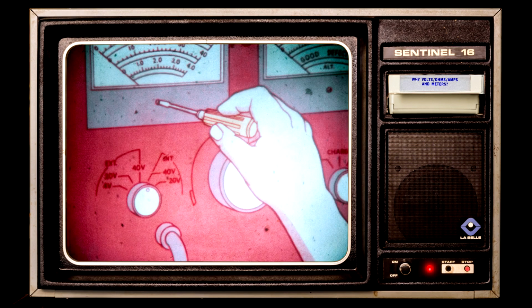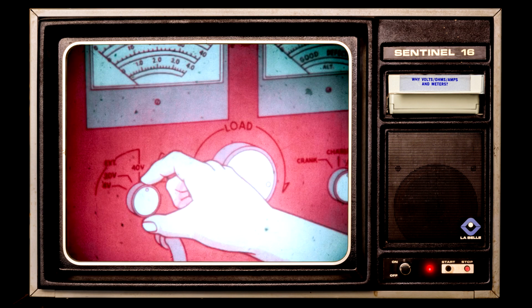Now let's concentrate on the 3 meters and put what you've learned to work. First, always make sure the meters you're using are accurate. Most meters can be zeroed by turning a small screw until the needle on the face lines up with the zero mark. The meter should not be connected to a circuit when you adjust the screw. Always set the meter range adjustment for a voltage or current higher than you expect to find. If the needle deflects less than half scale, set the range adjustment 1 step lower. This will help keep the meter accurate. For example, 12 volts applied to a voltmeter set for 4 volts will peg the needle and damage the meter.